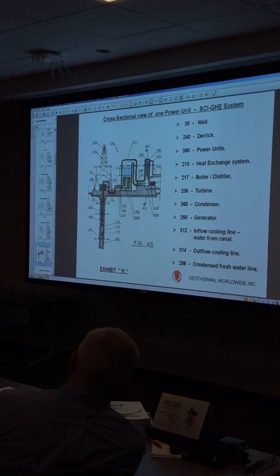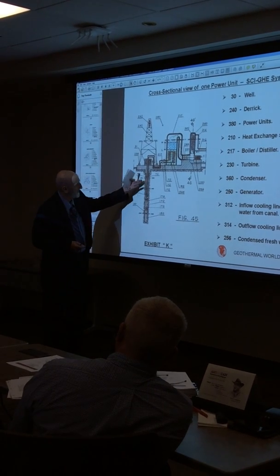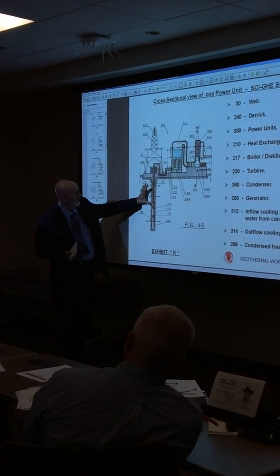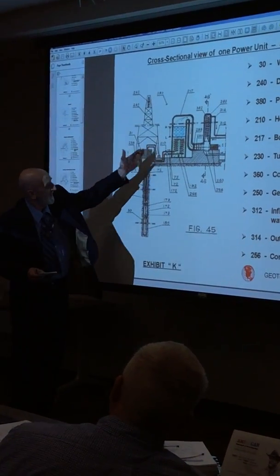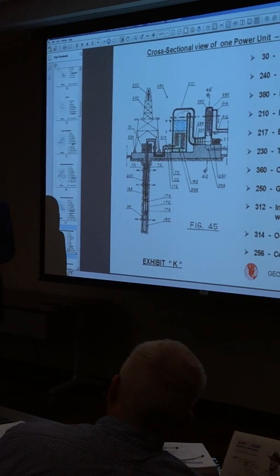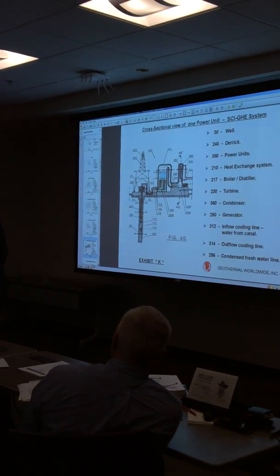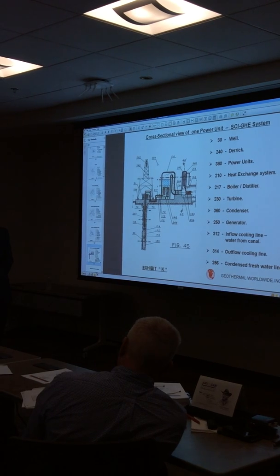Hold on, before you go any further, you're talking about putting a pump downhole. What depth? Below this, let's say 100 yards, 200 yards? This could be 20, 30 yards, it has to be proportional with this coil down. But even allowing for that, the geothermal resource at the Salton Sea is probably one of the most arduous, challenging generation potentials that we have, probably pretty close to in the world. Carbon steel will last no more than about 2.5 years. Titanium, depending on the grade, may last 15 to 20 years. How do you propose to make that reliable?